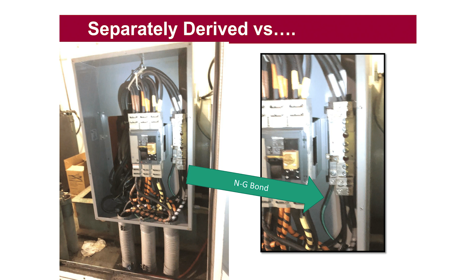This was done incorrectly where they were bonded together, where there was a mix of 3-pole and 4-pole transfer switches, but they had 3-pole transfer switches existing. So it should be a non-separately derived system. So this is the technician actually removing the bonding jumper from the neutral bus that was connecting the ground bus. So again, if you don't remember anything else, try to remember 3-pole, non-separately derived grounding, 4-pole, separately derived grounding.